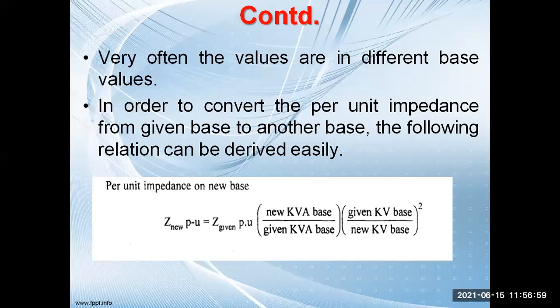Very often the values are in different base values. In order to convert the per unit impedance from the given base to another base, the following relation can be derived. Sometimes one base is given and you need to convert into some other base. This is some unitary method. So suppose you have an old base and you want to convert to a new base. Initially you have a 100 kVA base, but now in your system it is given as 500 kVA. You want to convert all the quantities given on the 100 kVA base to 500 kVA. So how to do that? In that case, your new per unit value is given by the new kVA base by given kVA base, into given kV base square by new kV base square, into Z given. So I hope if you know this, then it will be clear.